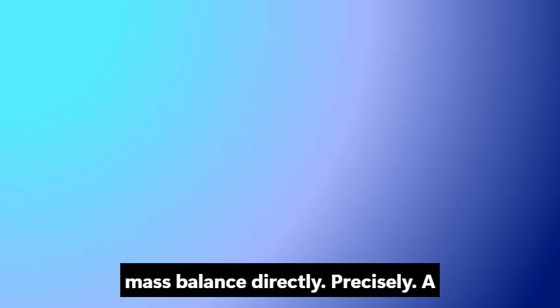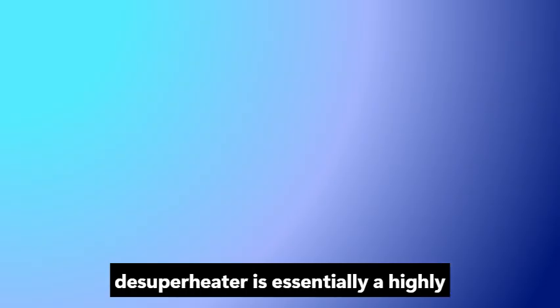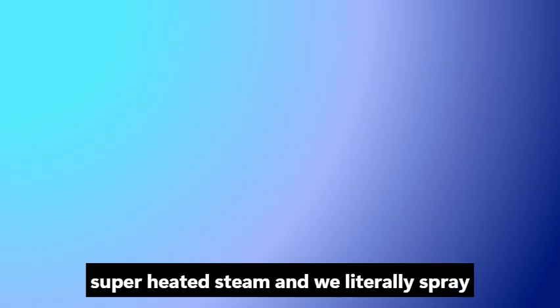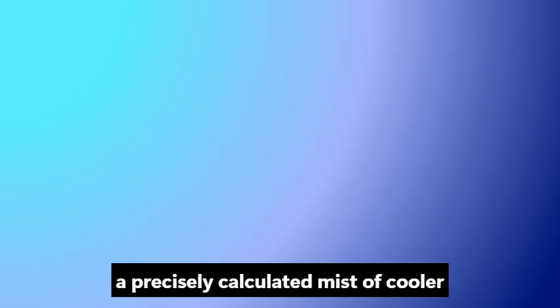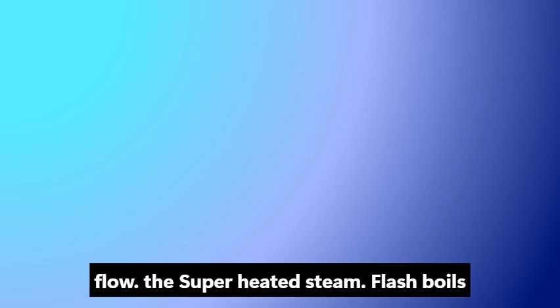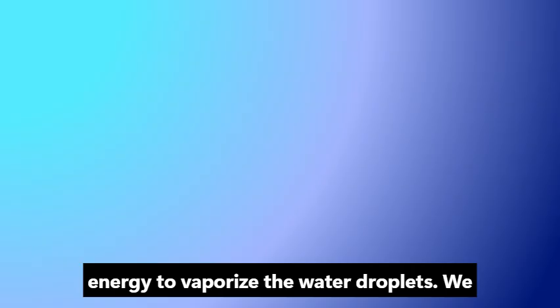Precisely. A de-superheater is essentially a highly engineered mixing valve. We take our superheated steam and we literally spray a precisely calculated mist of cooler liquid water directly into the steam flow. The superheated steam flash boils that mist. It gives up its own excess energy to vaporize the water droplets. We don't remove energy from the pipe, we just dilute it.